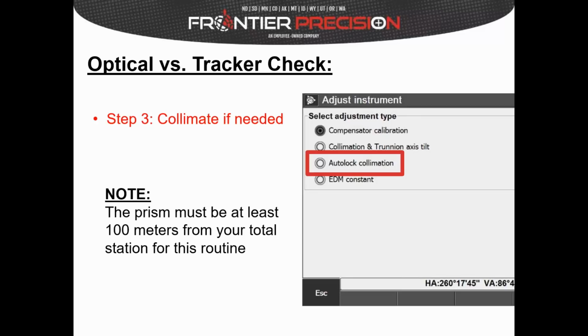And this is another one that you should be doing fairly regularly. I believe the spec on this one is to do it for every 15 degrees of temperature change. That might be a little overkill for the type of climate that we're in, at least here in Minnesota. That could be several times a day. But this is something you should maybe do monthly or something like that, just to make sure that things are checking out okay.